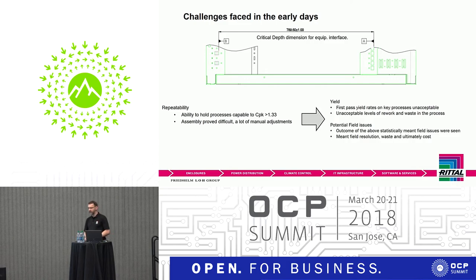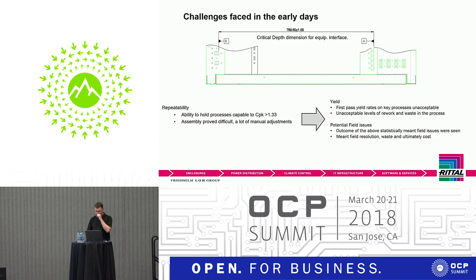The challenges faced in the early days of manufacturing an OCP rack: looking at critical dimensions we need to adhere to, the main one I'll focus on is the depth dimension for the equipment between the equipment interfaces — the 789.6mm dimension between the snapping location feature at the front and the stops at the back of the rack. I spoke last year at the workshop in Dallas about the dimension from the front equipment latching position to the busbar position, proposing specifications for the busbar-to-rack interface.